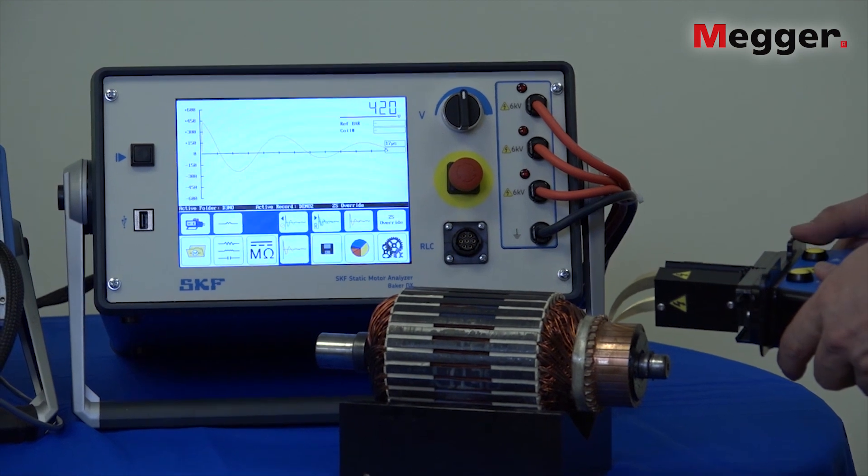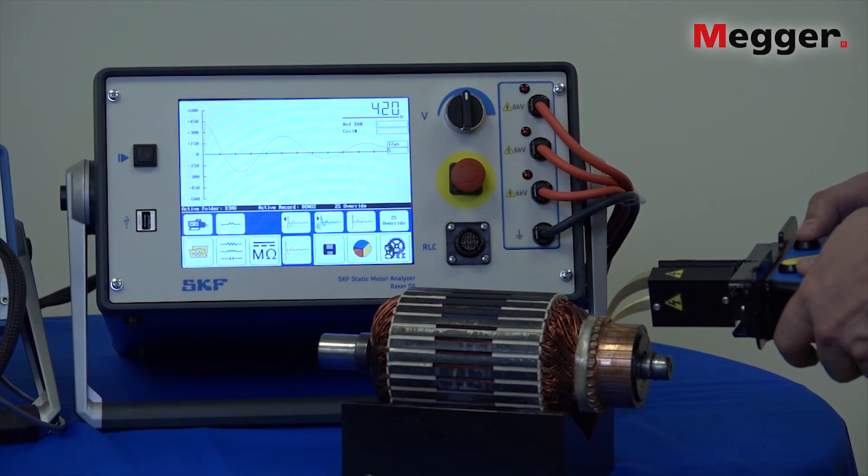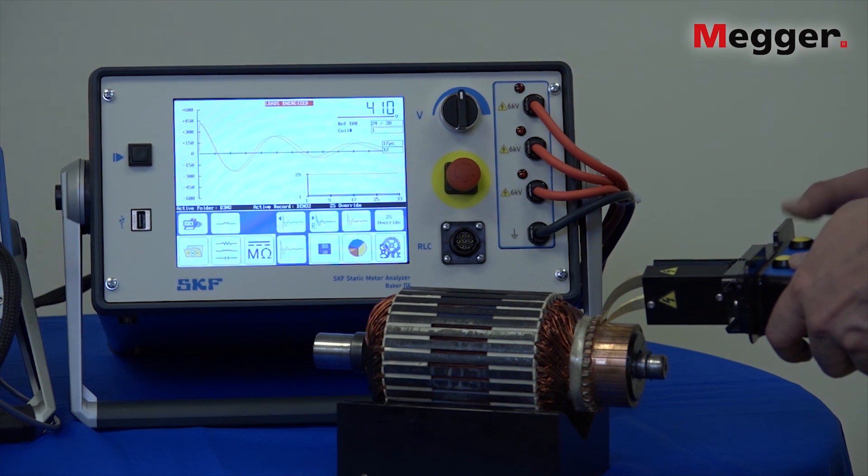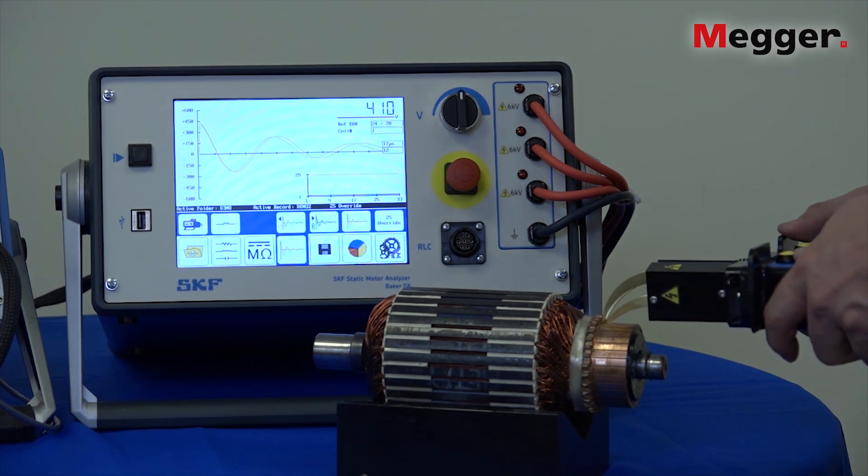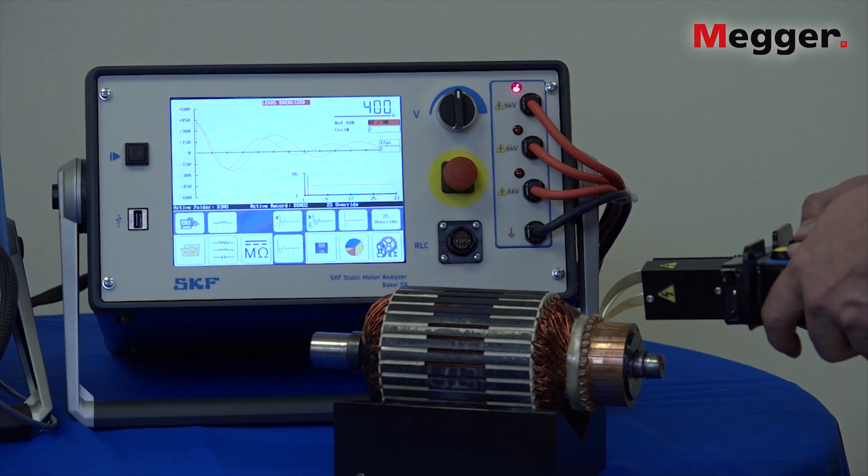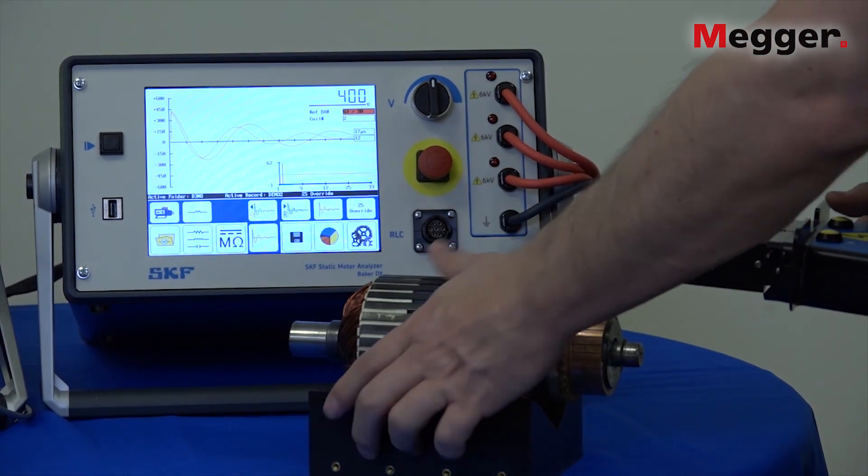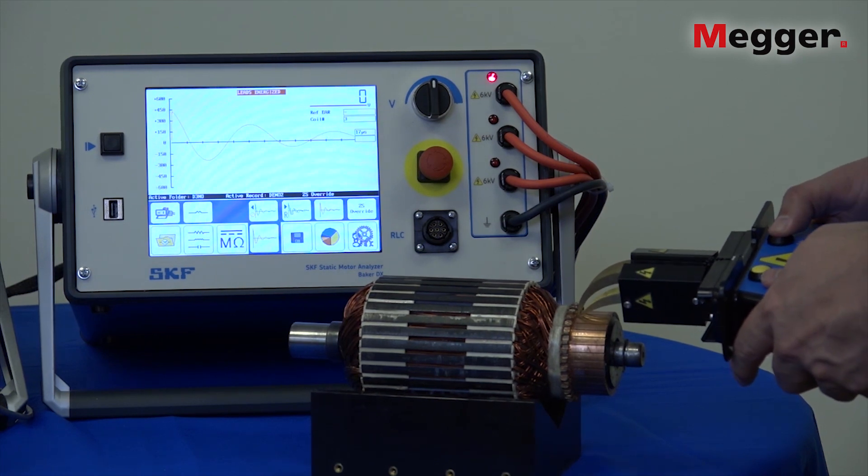So now I'm going to advance my commutator, put my probes down, hit the push to test button, and now we capture the second waveform and now just continue around the armature measuring each bar to bar surge pattern.